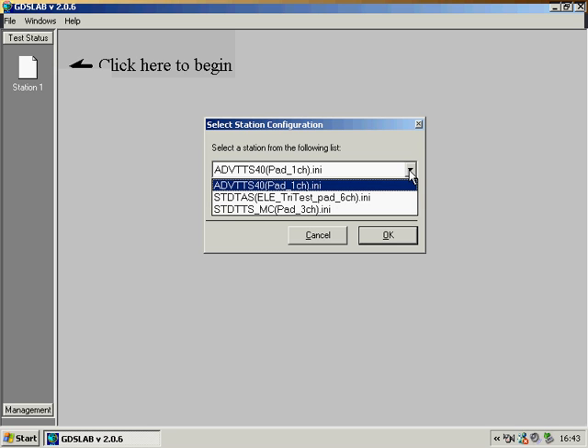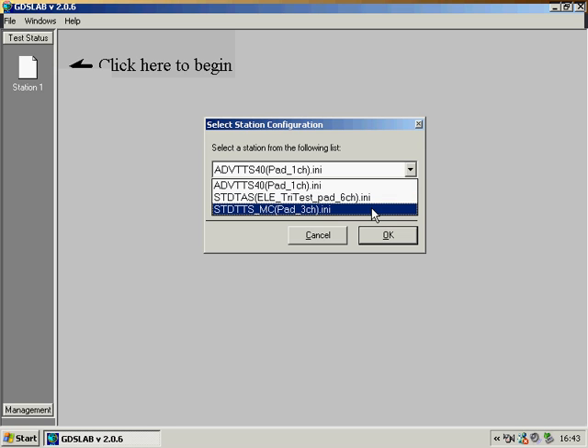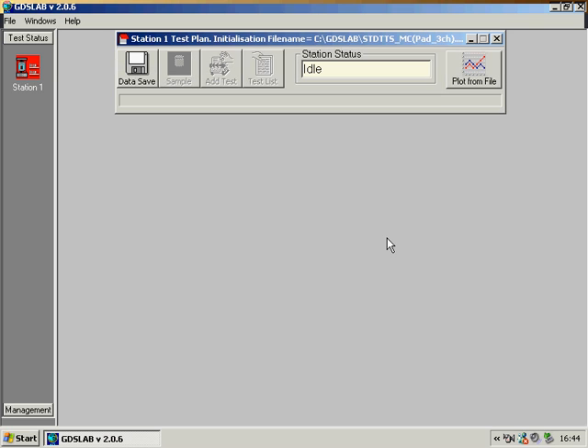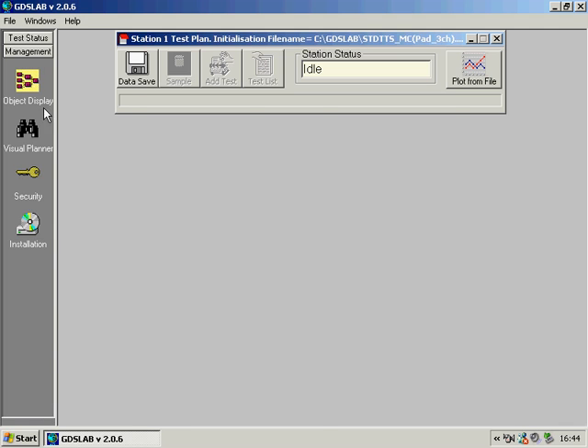For example, here, if I choose this file that I have made called STD TTS MC, this signifies a standard triaxial testing system using a motorized cell and a serial pad with three channels configured. When I go to the management, choose object display, I can see exactly the equipment as specified by that initialization file.